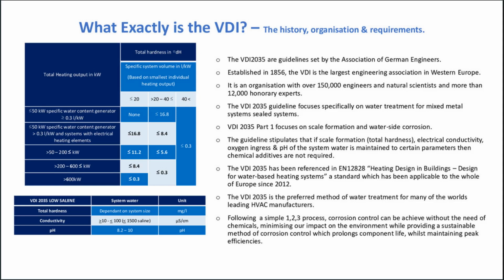The VDI 2035 has been referenced in EN 12828, heating designs in buildings, designed for water-based heating systems, a standard applicable to the whole of Europe since 2012. The VDI 2035 is a preferred method of water treatment for many of the world's leading manufacturers. Following a simple 1-2-3 process, corrosion control can be achieved without the need for chemicals, minimizing our impact on the environment, while providing a sustainable method of corrosion control which prolongs components' life while maintaining peak efficiencies.